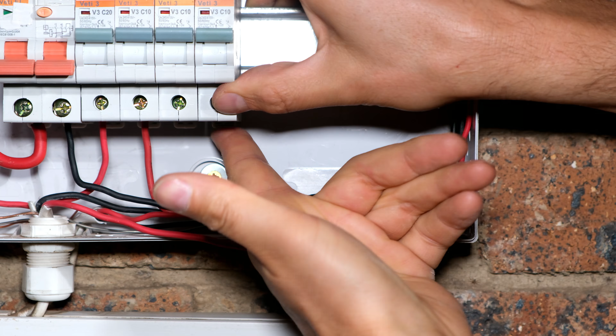Right, so in this case, I just need to get power to this circuit breaker, which is going to feed my timer. So I'm going to use this bus bar. I'm going to insert it, and notice that it is joined to the other circuit breakers in the row. Where does it get the power from? It gets it from this wire, which comes from the main circuit breaker, and there the in-feed goes through the circuit breaker to this wire.